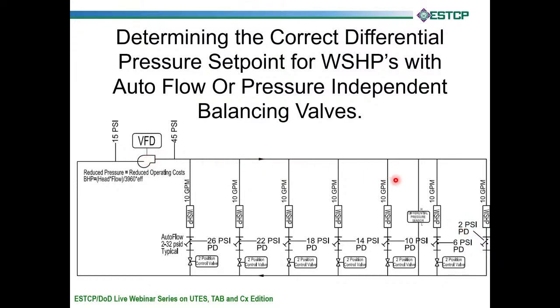And this differential pressure that is measured right here by this transducer is sending a signal to a controller, and the controller is going to the pump. In that case, you would need to lower your differential pressure set point. You would lower that set point until the VFD slows its pump down until you get very close to 2 psi on your most remote circuit. That would indicate that this valve is fully open and your pump is running no faster than it absolutely has to. That is kind of the definition of a system being balanced.